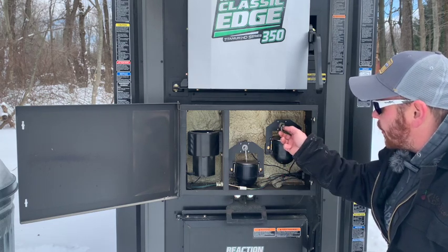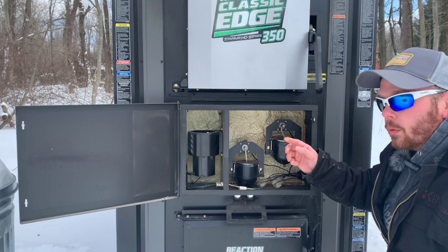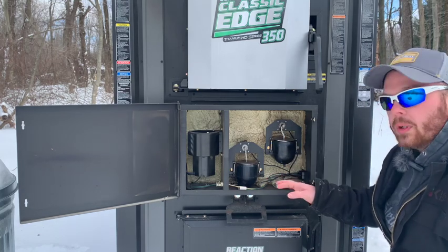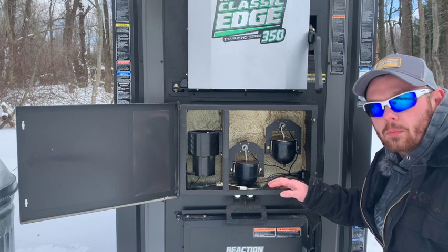So the dealer thinks that there's something wrong with the stepper motor here, so we're going to change it. I've got the new one on the bench, so I'll pull this all off. We'll go in the house and I'll show you what we've got to do.